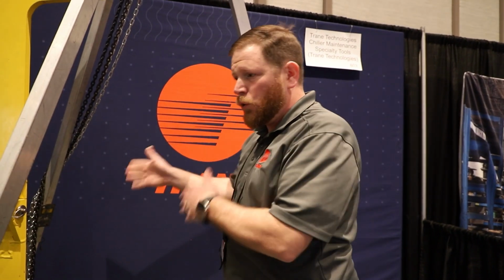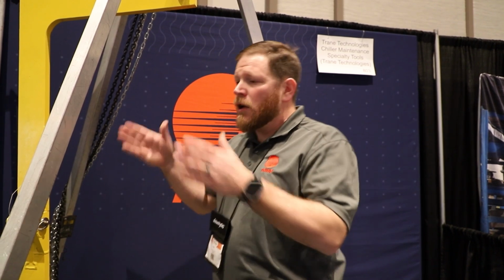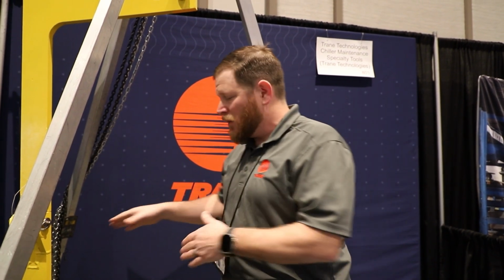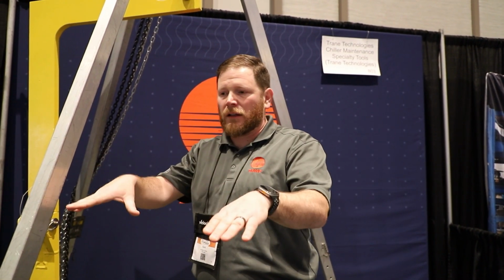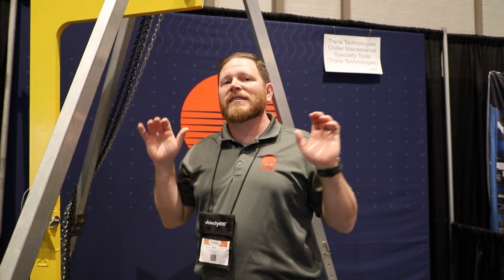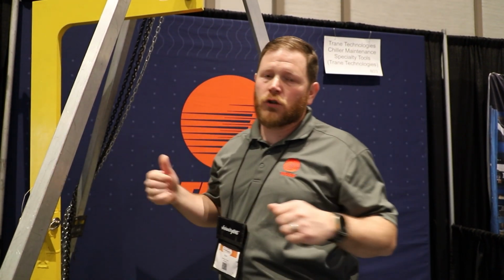As a tech now, when I go to remove and replace that using the skyhook, all I need to do is remove 4 bolts from the bottom of the compressor that hold it in place, and free up the piping section. The skyhook will access the compressor directly in its place to be removed, then set the new compressor directly back into place. No more muscling the compressors around.